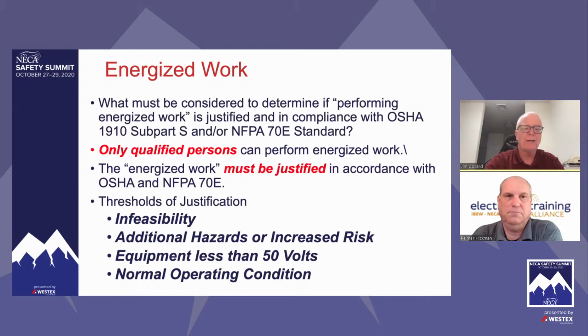So Palmer, you and I go into a building that's 20 years old, still seems to be in decent shape. And there's nobody in that building that knows anything about their distribution system. Can we make a determination that any of that has been properly maintained? Absolutely not. That is probably one of the most common occurrences. So probably a common theme we've all seen in edition after edition of 70E is the importance of maintenance. And quite frankly, that's one thing that I wish we could do better as a committee to give better guidance to the industry, but we really can't.